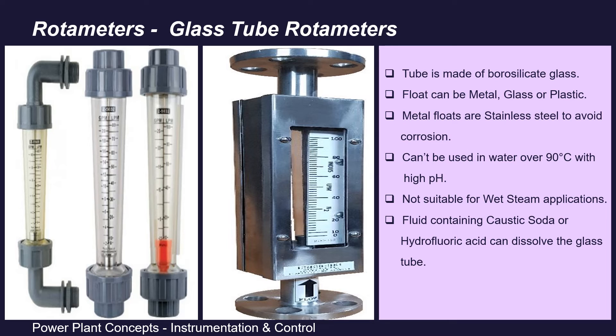In glass tube rotameters, the tube is made up of borosilicate glass and the float can be metal, glass, or plastic — in case of metal floats, stainless steel is preferred to avoid corrosion. Glass tube rotameters cannot be used in water over 90°C with high pH, which softens the glass, nor in wet steam applications. Moreover, if the fluid contains caustic soda or hydrofluoric acid — which dissolve the glass itself — these rotameters cannot be used in those applications.